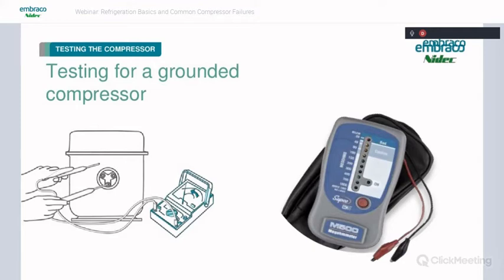And you might have a compressor that's still running, but you might read it and it might be in the yellow. It could even almost show red and still be running. If you find this, you're going to want to go ahead and let the customer know that the insulation is breaking down on this compressor, and they could very well have a short, have a compressor go to ground and quit working very soon. It's a good indication that a compressor is getting ready to go out. So very, very good tool to have on your truck, the megohm meter, to test compressors.